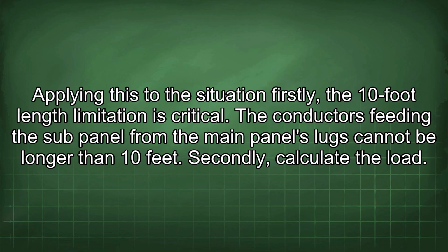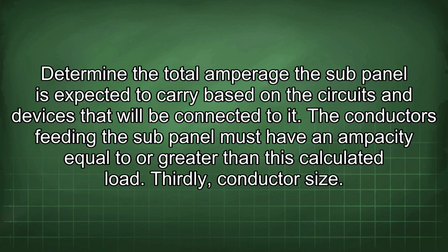Applying this to the situation, firstly, the 10-foot length limitation is critical. The conductors feeding the sub-panel from the main panel's lugs cannot be longer than 10 feet. Secondly, calculate the load. Determine the total amperage the sub-panel is expected to carry based on the circuits and devices that will be connected to it. The conductors feeding the sub-panel must have an ampacity equal to or greater than this calculated load.